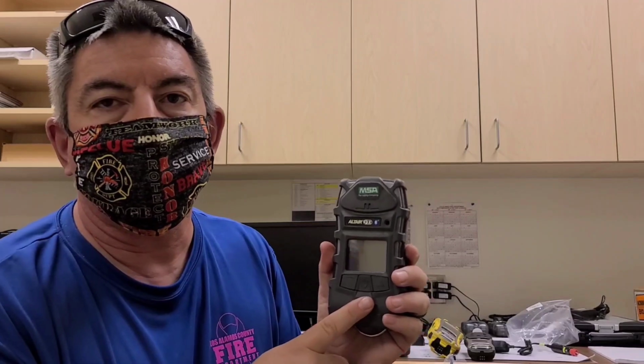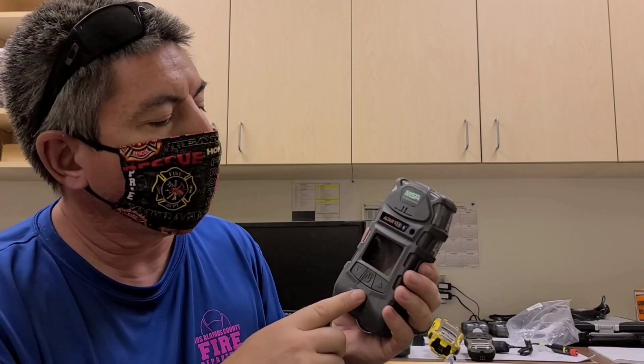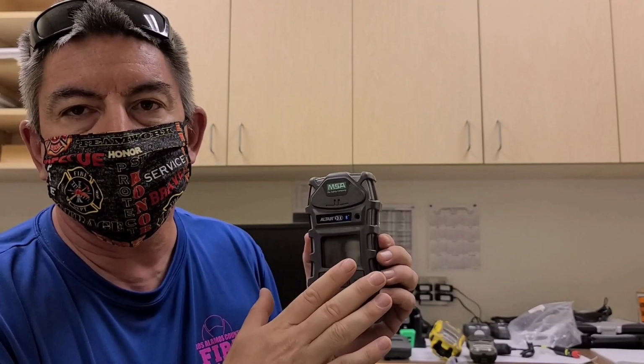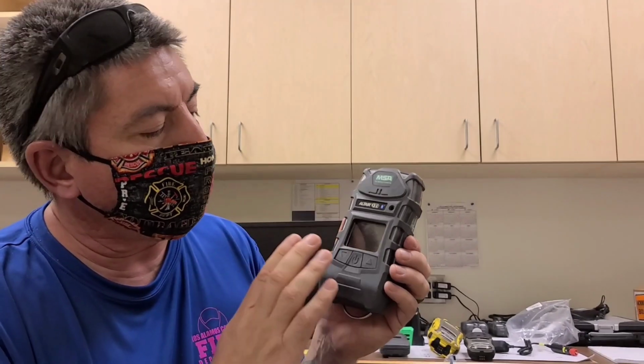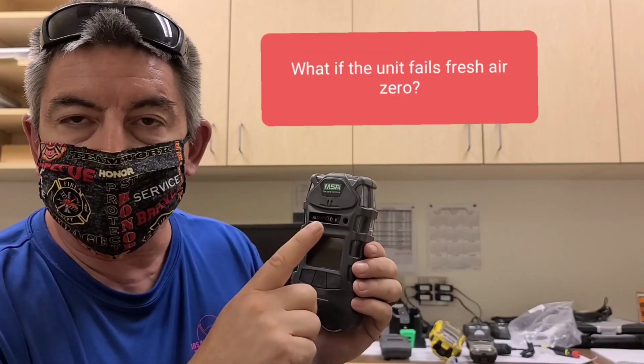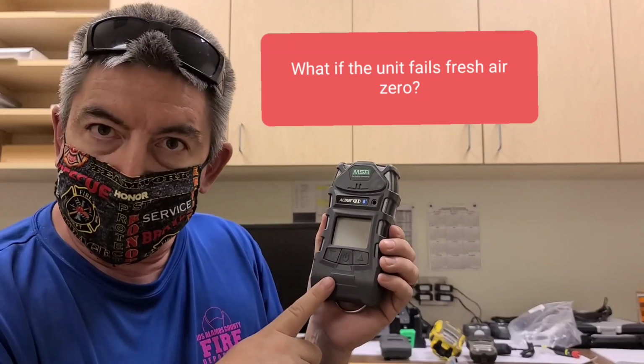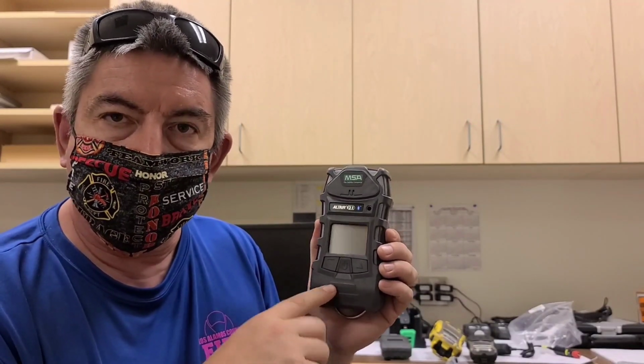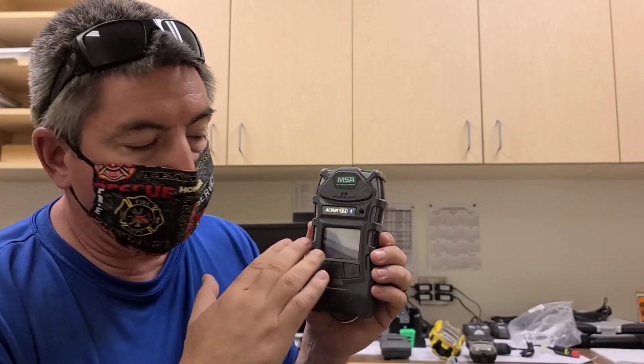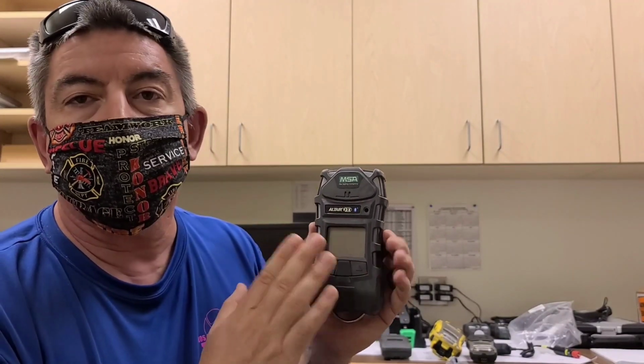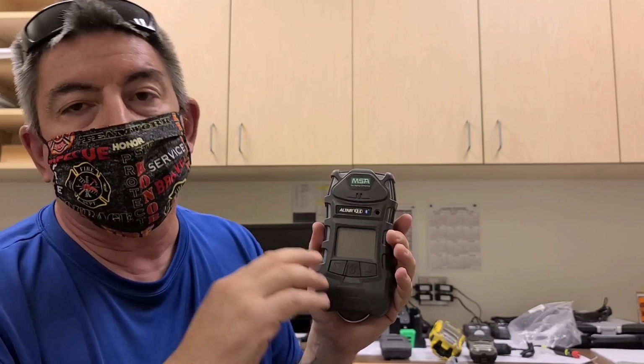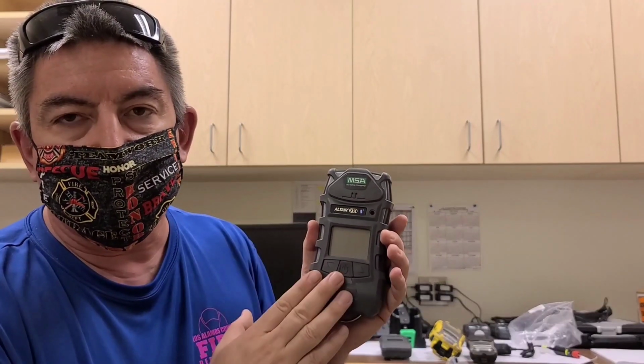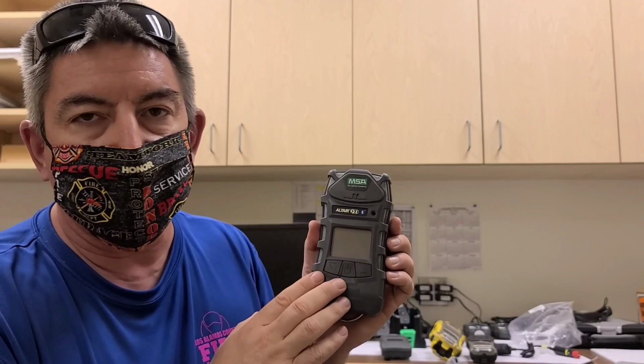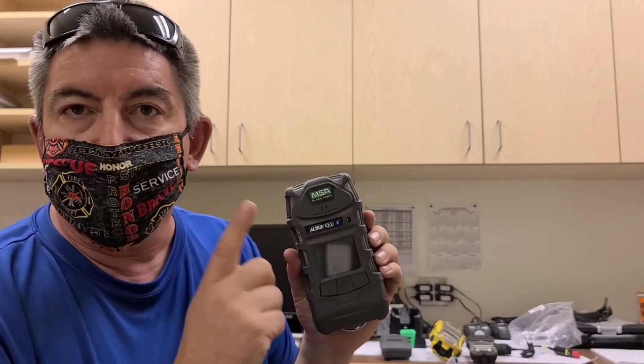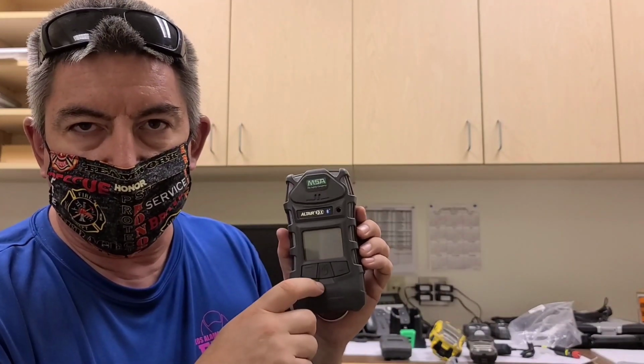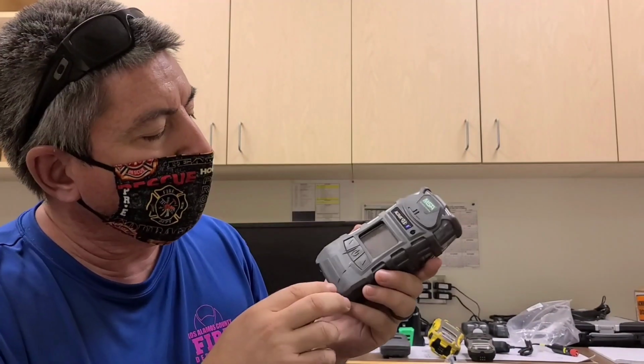So once the pressure calibration is complete, it's in measurement mode, all those sensors have been set to 0, you're good to go. If you do get a fault, one of them doesn't have a check mark, repeat the process, do one more fresh air calibration, and if it corrects, all of them check off, everything's corrected, then the unit's good to use. But after that, if upon the second time you've tried to do a fresh air cal and it doesn't correct any sensor that was giving it a problem, the unit is not usable. We'd have to recalibrate it and figure out what's going wrong with it.